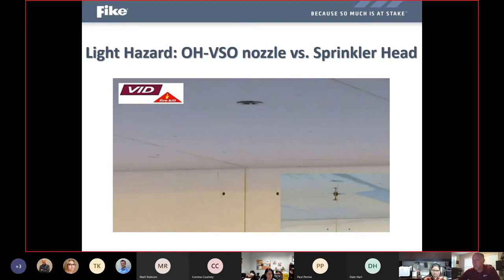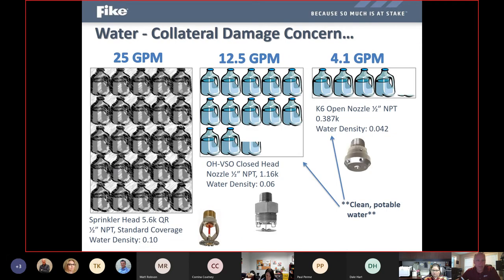If we look at a video here, if this one plays, we've got a water mist nozzle up in the main screen versus a traditional sprinkler head down in the right-hand corner of the screen. You can see when that mist sprays off, it floats around and looks like a cloud inside the room. So it almost acts and behaves like a gas when it discharges, and because of that, it will be very quick to put out a fire. And when we discharge it as a mist, we use a lot less water than a traditional sprinkler system.